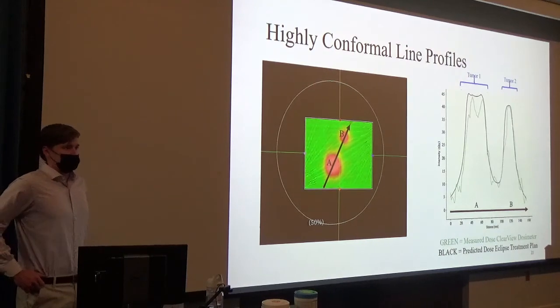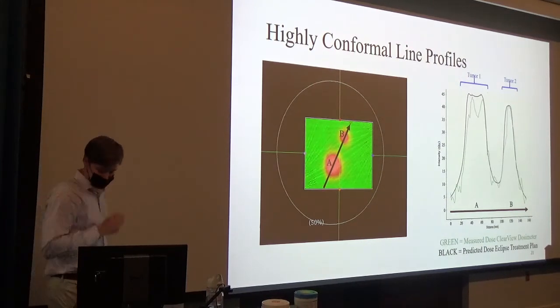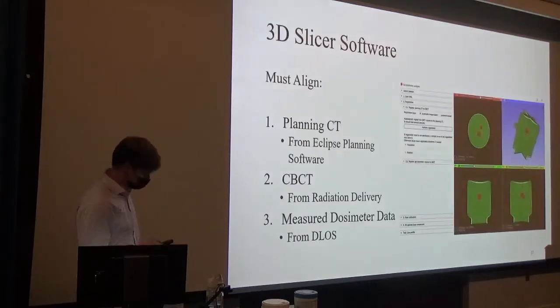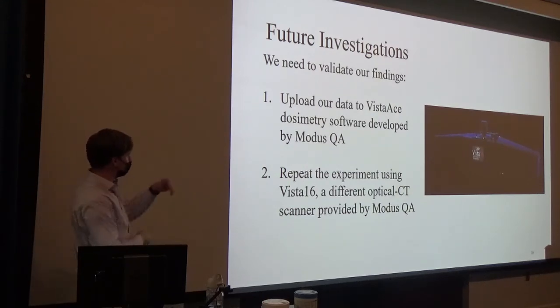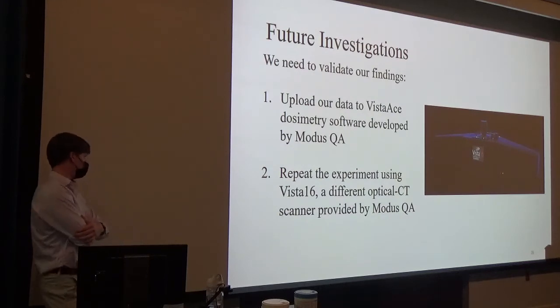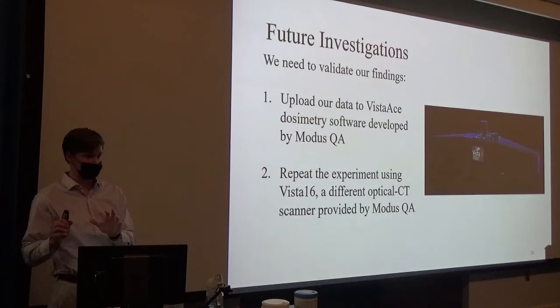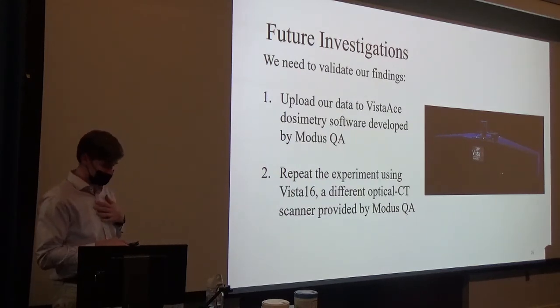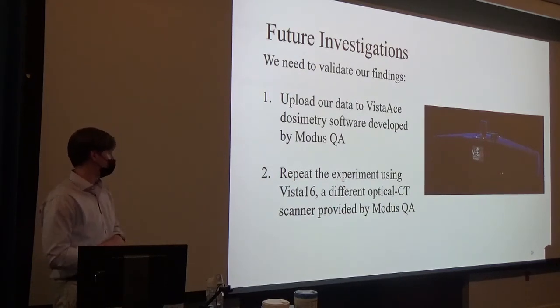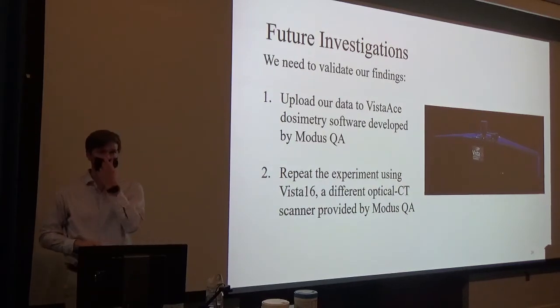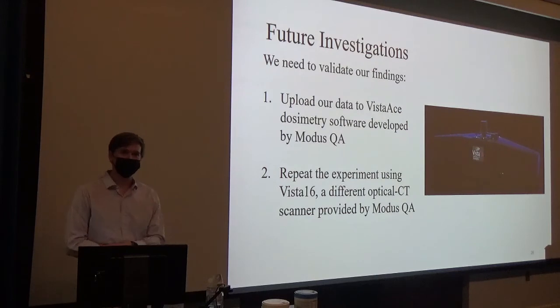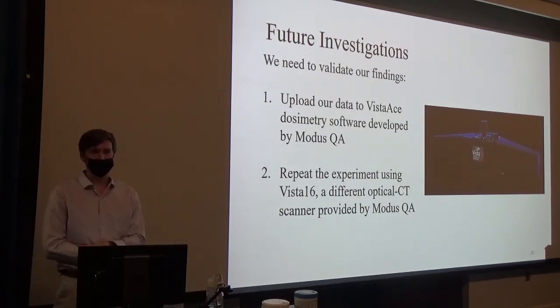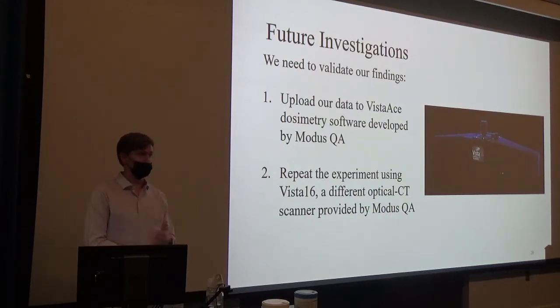Question: What's the next step? We're looking to validate our results. I've trained up the student replacing me on the same software, and the company that makes the dosimeters has agreed to train her on their new software called VistaAce. We'll upload our data from our scanners into their system and compare results. They've also agreed to send a different optical CT scanner to repeat the experiment to validate the results. As for why QA is still in 2D while everything else is in 3D — that's really the problem. We're trying to model 3D tumors with 2D films, and there's inherent inaccuracy there.